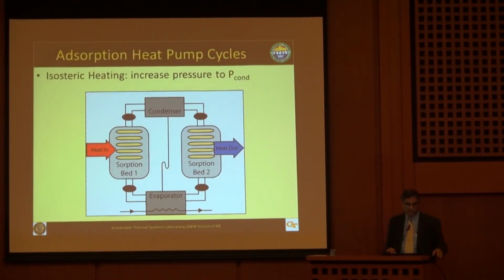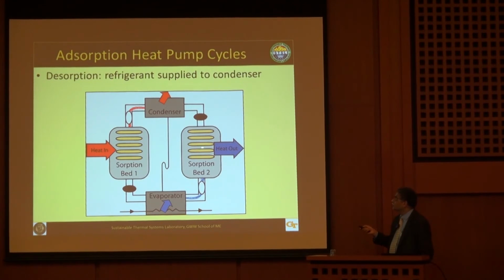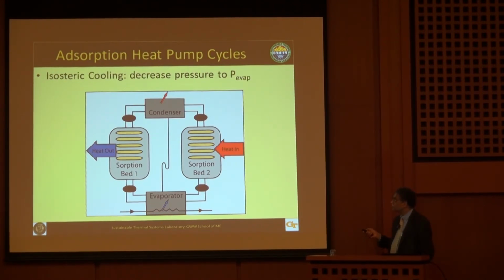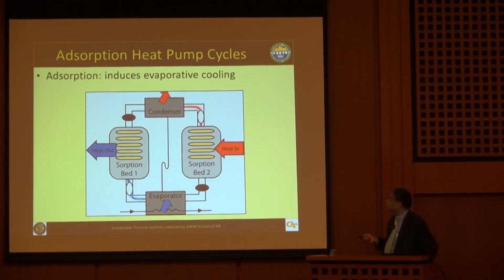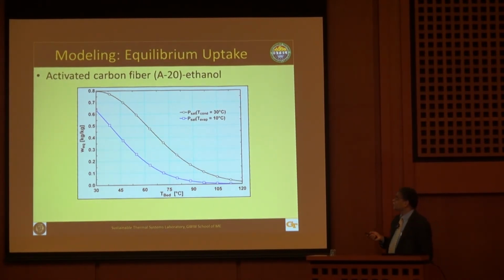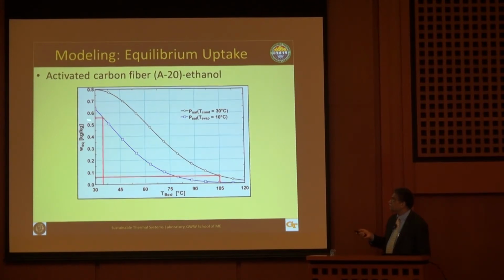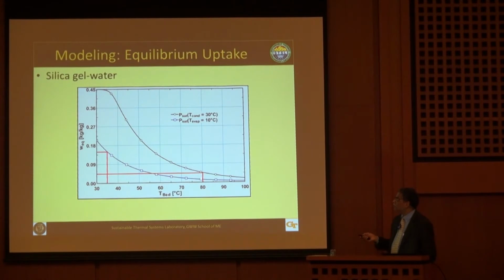We're also doing adsorption research, and there's a lot of expertise in this room—Professor Saha has worked on adsorption for many years. This works as a batch process: you take a bed and put heat in, which desorbs the refrigerant, then it condenses. After that phase ends, you cool it so the refrigerant gets adsorbed back in, enabling the evaporation process, then you switch. You can use one bed, or two beds phase-lagged to provide relatively constant cooling. You can use different working fluid pairs—for example, an activated carbon fiber ethanol process with different isotherms—to determine how much bed mass you need to support a given amount of cooling. This lets you pick the right working pair combination for the waste heat source available.